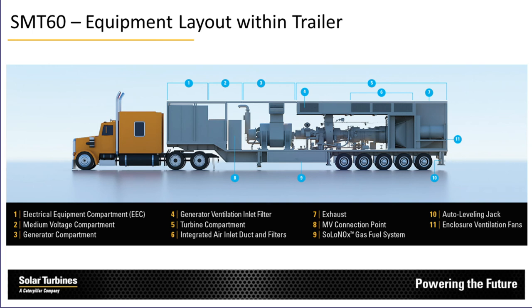And depending on the gas components, it can cause issues. There's a term called the Wobbe index, which talks about the gas intensity, if you will, the fuel density, the heat content of the gas. What's really great about this system is that it has really wide fuel flexibility built into the design. So you can use straight-up methane if it's available, or whatever gas is coming out of the ground, which is really the key purpose here. Instead of flaring, use that gas, and off you go.